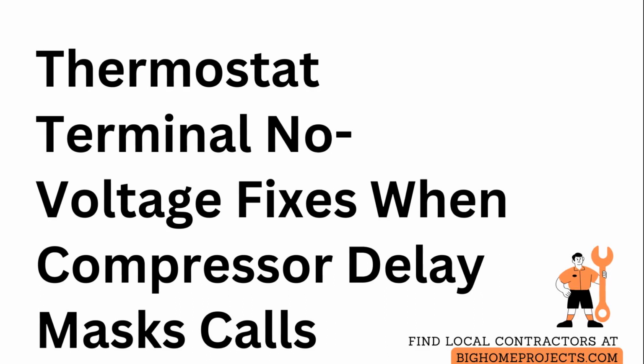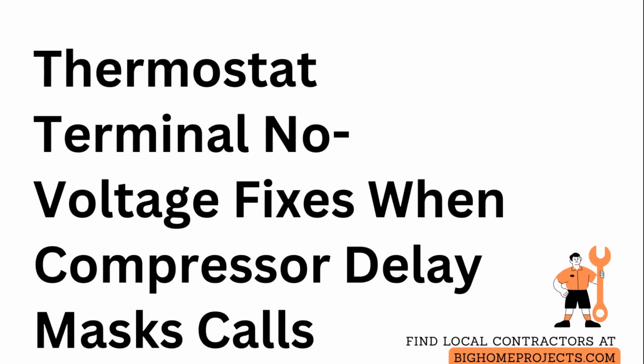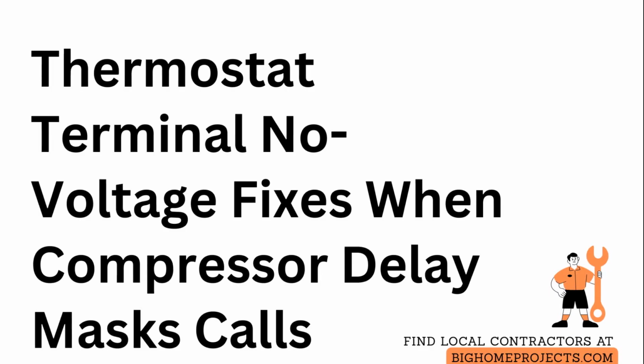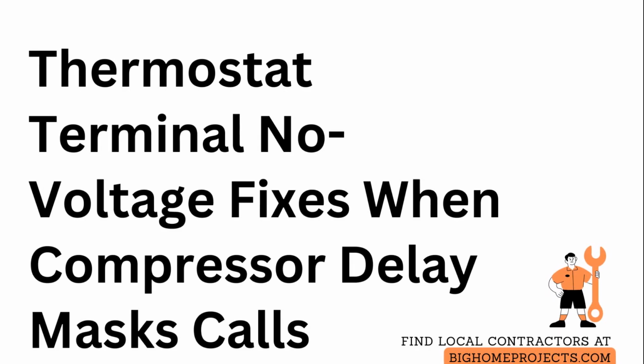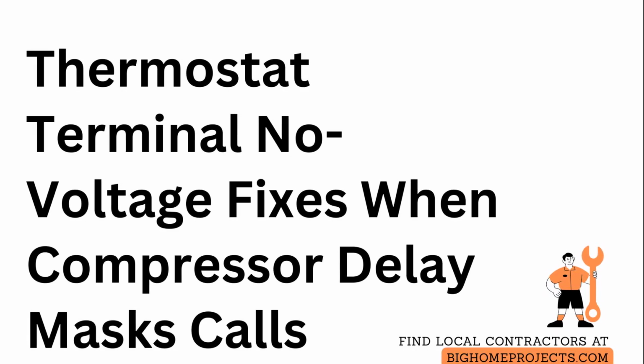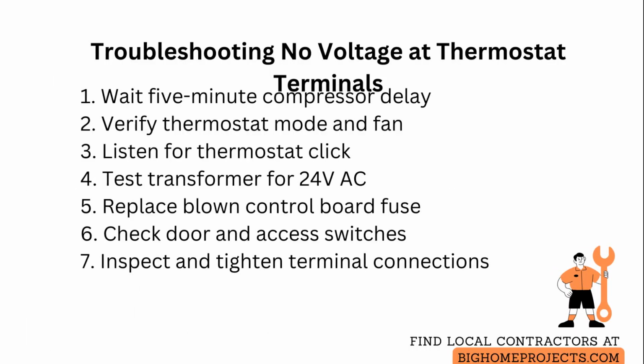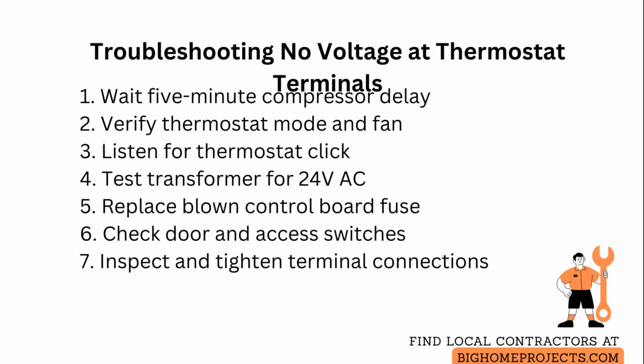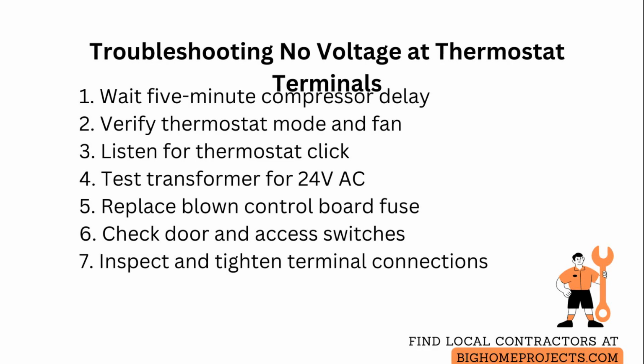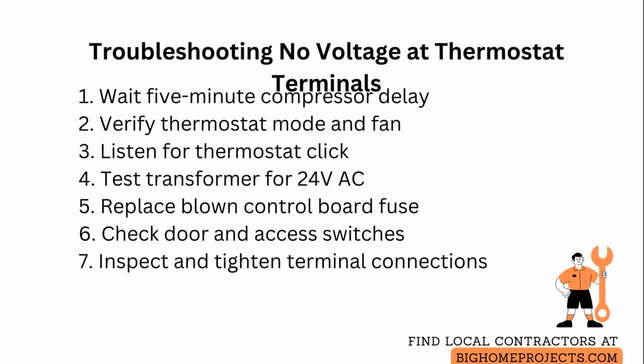Thermostat terminals can show no voltage even when the thermostat appears powered and set because of overlooked procedural delays or component failures, preventing a control signal from reaching the system. Check for the common 5-minute compressor delay that many cooling systems enforce after recent shutdown. This factory safety delay prevents immediate compressor restart and will show no call for cooling at the outdoor unit even though the thermostat indicates cooling.